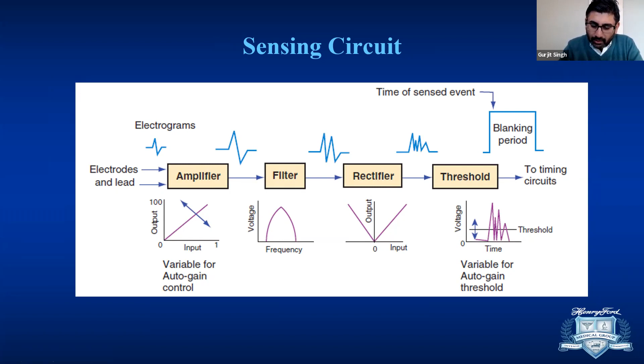So it's not that the pacemaker is going wrong. The pacemaker is doing its job. It's just the way you told the pacemaker to deliver the ventricle signal at the same time, which happens to be close to the patient's own conduction. So this is an example of a functional non-capture due to prolonged AV delay.